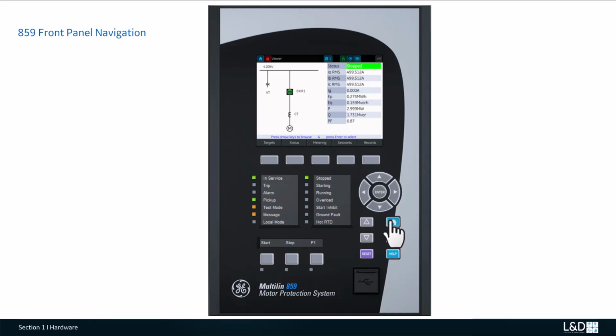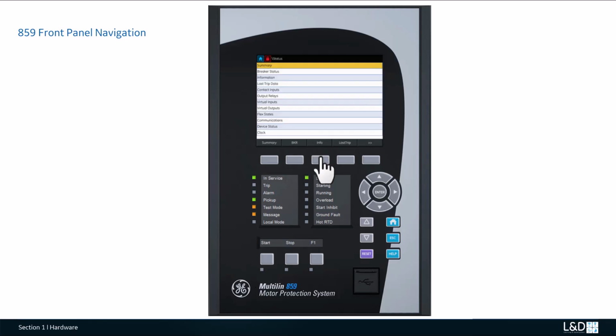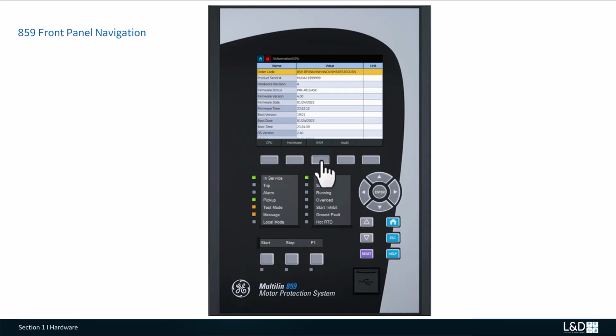So as we know, in the 369, the main hierarchy menu structure is actual values and set points. In the 8 Series, there are 5 menu tabs associated with the navigation push buttons: targets, status, metering, set points, and records. So now if I want to check the order code, I can click this status.